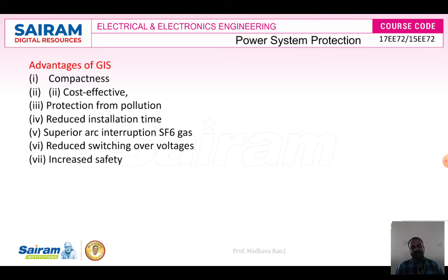It is compact, very small in size, the cost is less, and there is protection from air pollution. Noise will not be there. Installation time is reduced, since it has fewer pieces of equipment. Next, superior arc interruption: within a fraction of a second, SF6 gas will interrupt the arc. And it reduces switching overvoltages, so voltage oscillations will be less. It increases safety. These are the advantages.